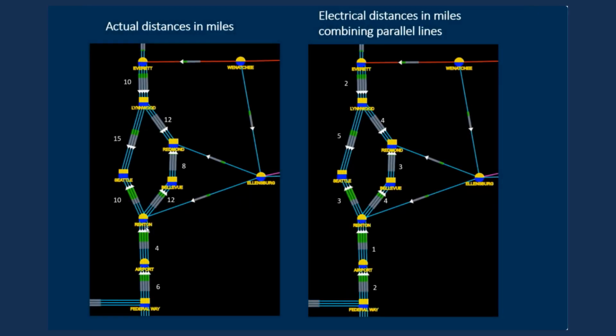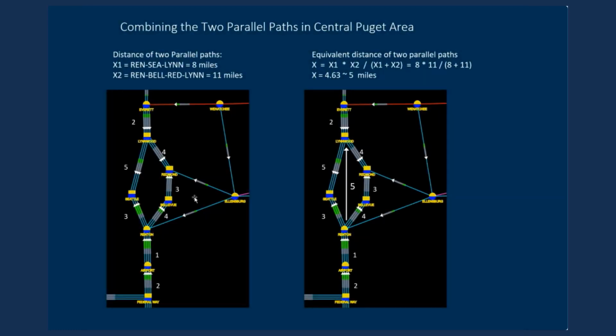Now, in the case of the Puget system, we have this path from Renton to Lynnwood that goes either through Renton to Seattle to Lynnwood, or Renton to Bellevue to Redmond to Lynnwood. And sometimes we want the effective length of the path all the way between Renton and Lynnwood directly. So again, this is the equivalent line length when we've done the parallel combination. So we had 15 with 3 lines in parallel, that converts to 5. We had an 8 with 3 lines in parallel, and we round that up to 3. But here we'll take the combination of this path in parallel with this path.